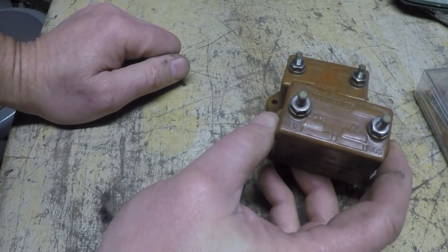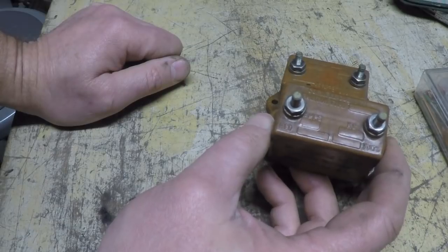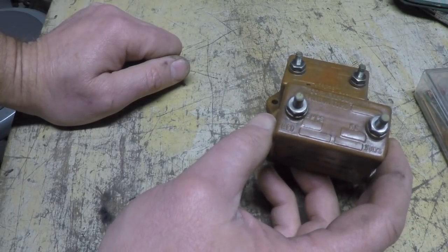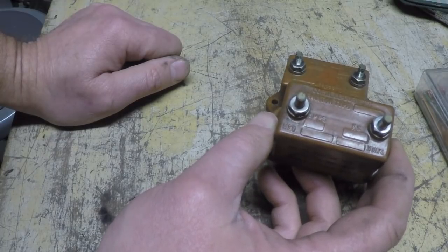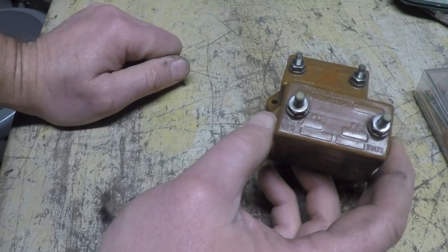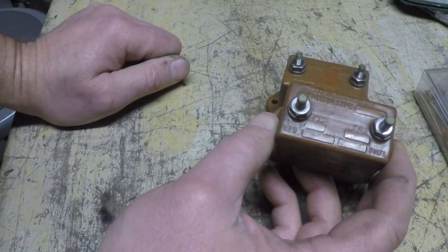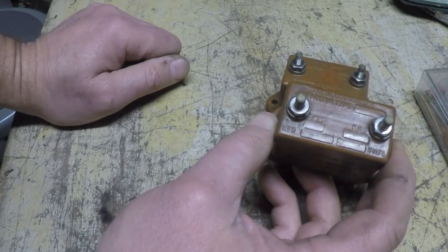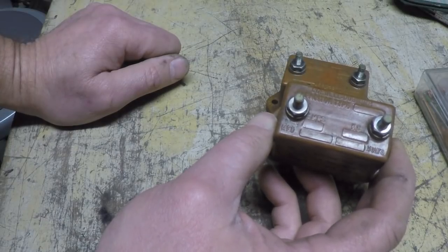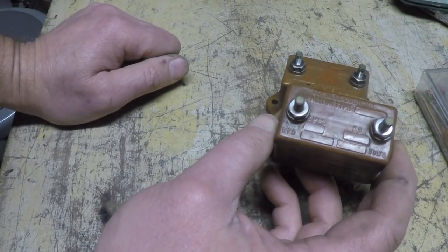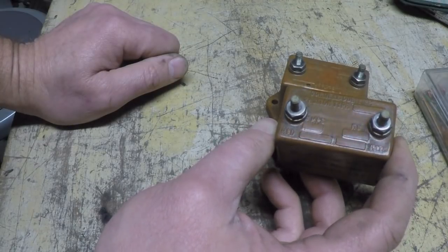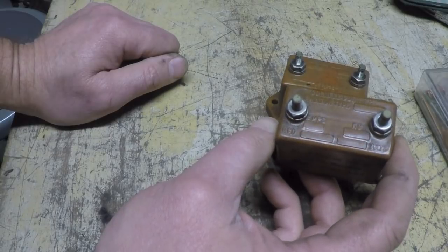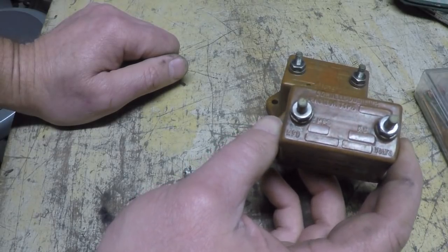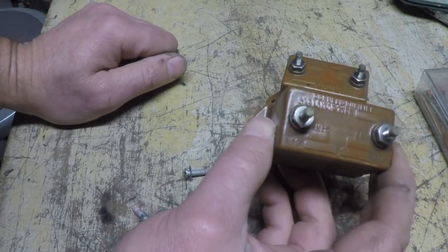So you can put a higher voltage rated capacitor into a lower voltage rated, but you can't go vice versa. In other words, a 10 kV cap can be put in the place of a 5 kV cap. In fact, it's going to give you more longevity, as long as you can physically fit it in there. But you want to have the microfarads stay the same. On the other hand, you can't take a 5 kV cap and put it in to replace a 10 kV, because the 10 kV is there because the circuit's got more than 5 kV of voltage in there, so that cap will fail quickly. And as a matter of fact, if you put too low of a working voltage cap in there, it will fail violently. Violently would be the best way to put it.